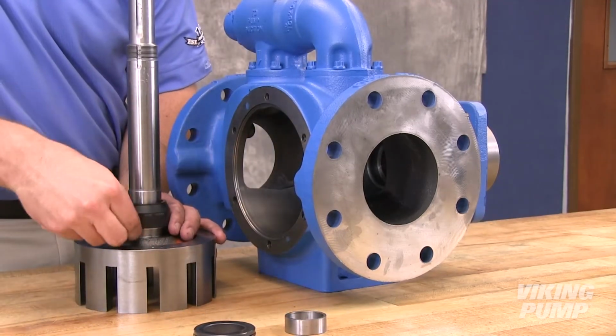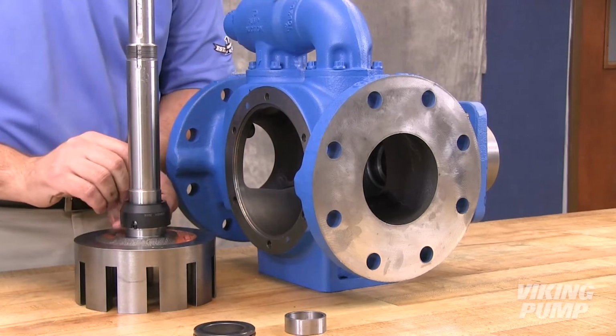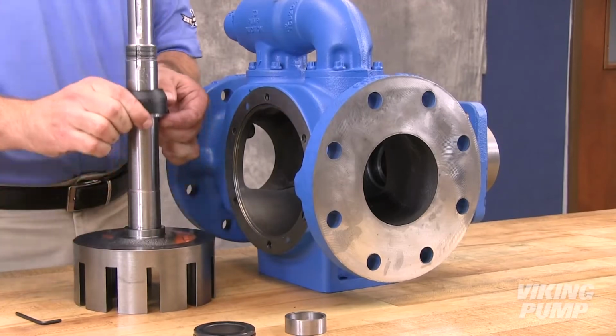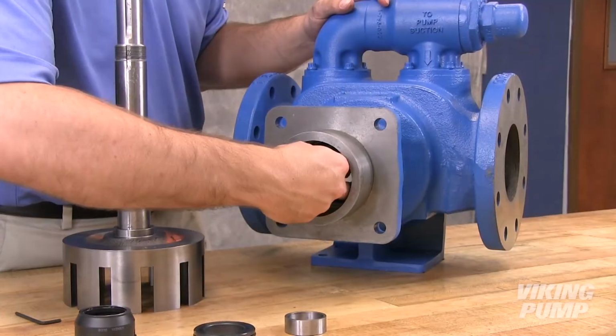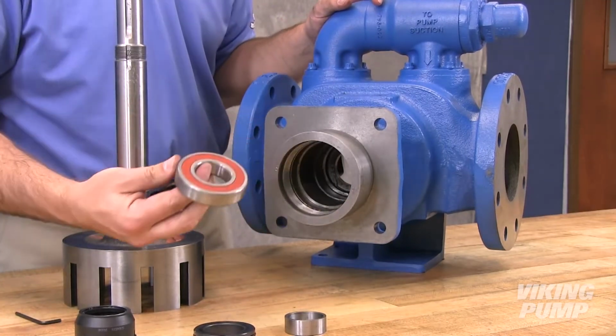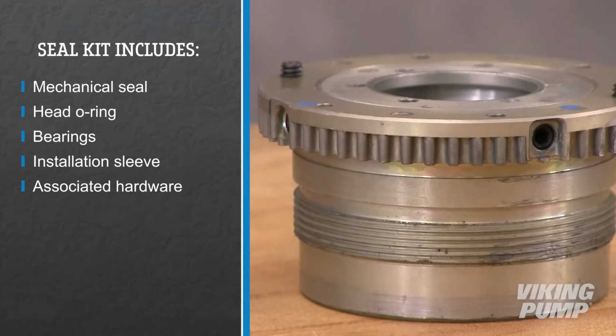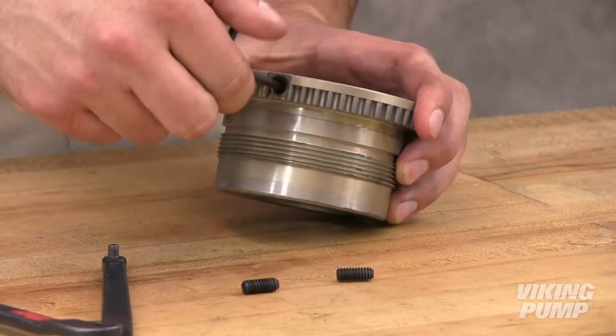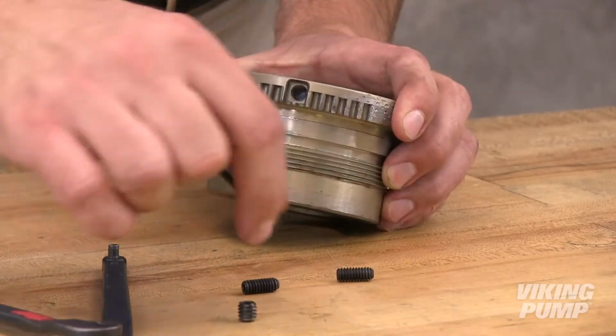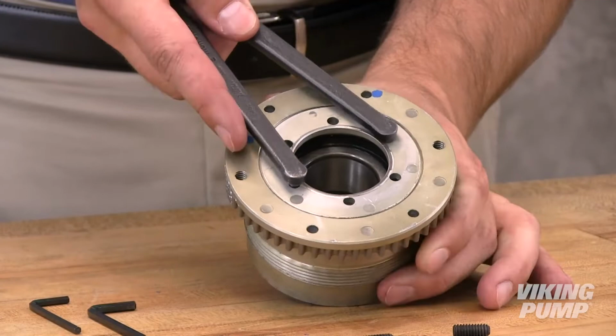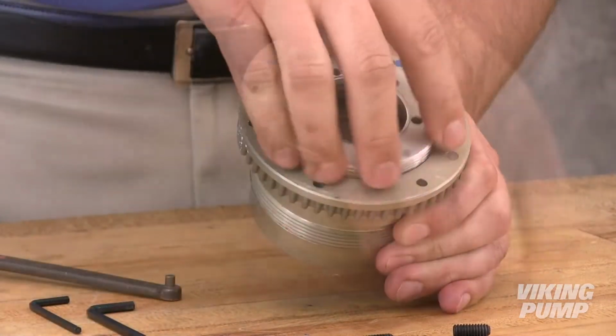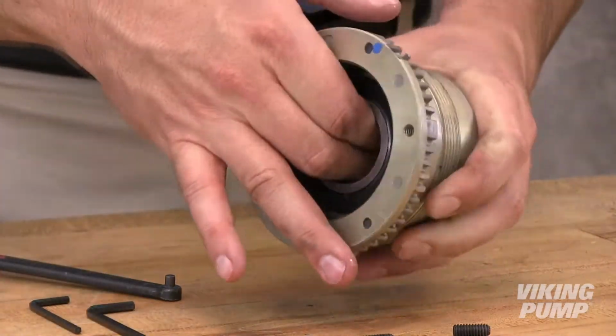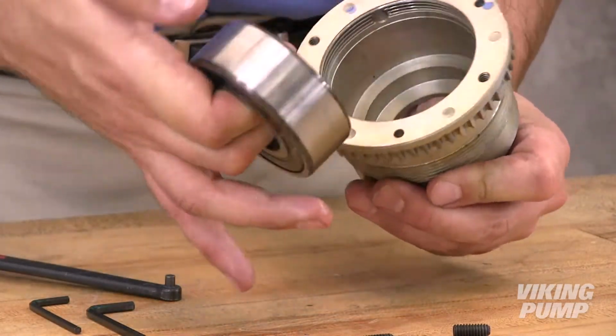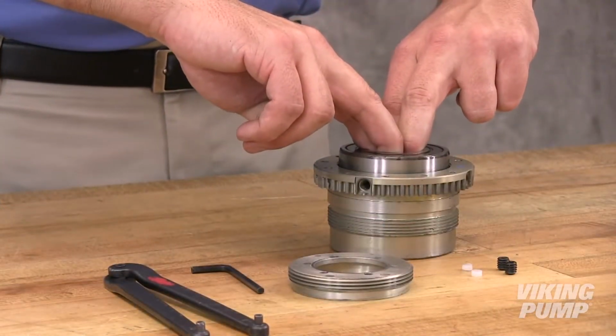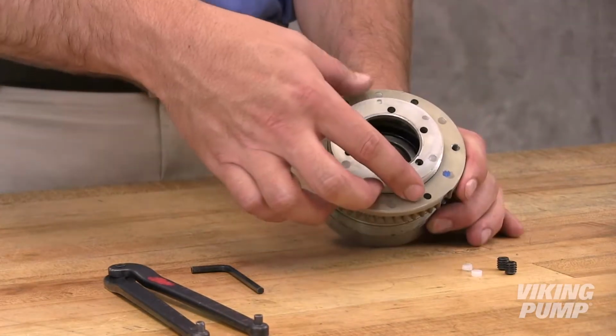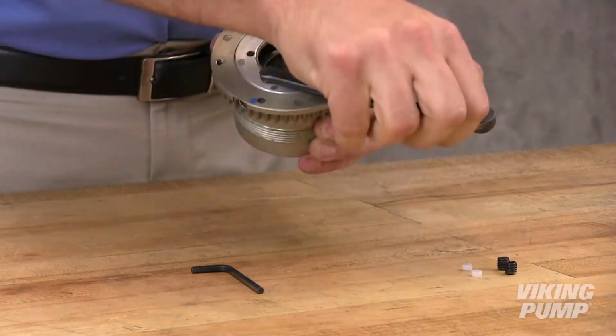Loosen the set screws on the mechanical seal and remove the seal from the shaft. Remove the inner bearing from the casing. The outer bearing is located in the bearing housing. To access, the bearing end cap will need to be removed. Loosen and remove the radial set screws. Remove the end cap using a spanner wrench. Remove and replace the bearing. Make sure to replace the bearing end cap, set screws, and PTFE plugs as well.